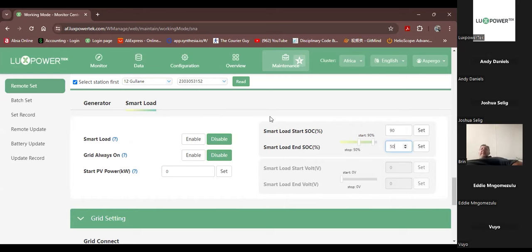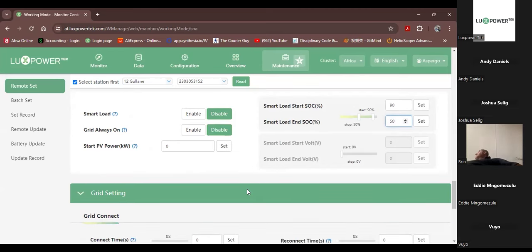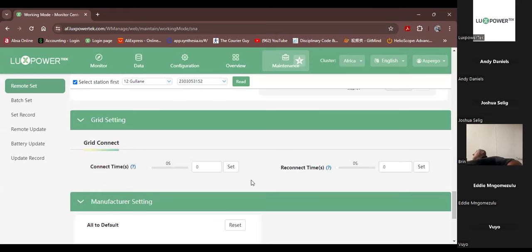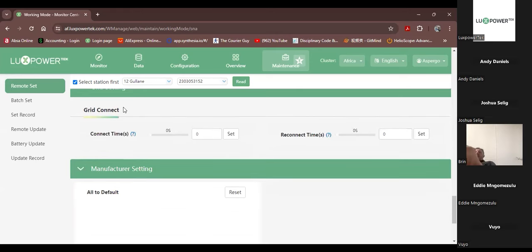Power will go into the smart load, and we will have a new feature here, and the machine will also be able to do frequency shifting. So in other words, when the batteries are fully charged, then it will shift the frequency so that the on-grid inverter can start derating its output power until it will switch off completely. Right, and this feature here is probably my most exciting feature to introduce to you today.